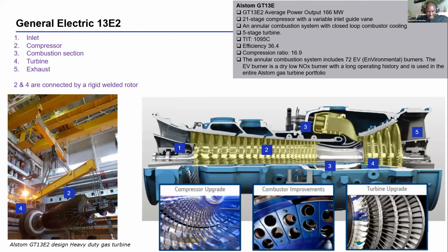so that it can run. But companies like SULZER do not believe in this concept. That's the difference. So SULZER can tell you, no, you don't need to change your rotor at 200K. Send it to us. We'll do a lifetime extension of the rotor. Then you can still run your rotor for almost one more cycle. And one more cycle is another 200K. Or we tell you, based on what we see at the inspection, maybe you can run another half cycle, 100,000 hours.